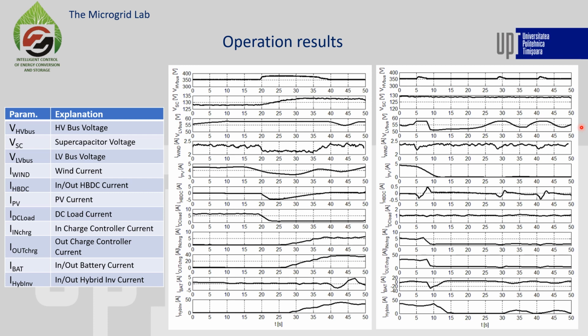For the first case, all renewable energy sources generate energy. At the beginning, the DC loads absorb all the available power, maintaining the voltage of the high voltage DC bus at 350 volts. The charge controller is not active because it only starts at 355 volts, and we can see that its input and output current are zero.